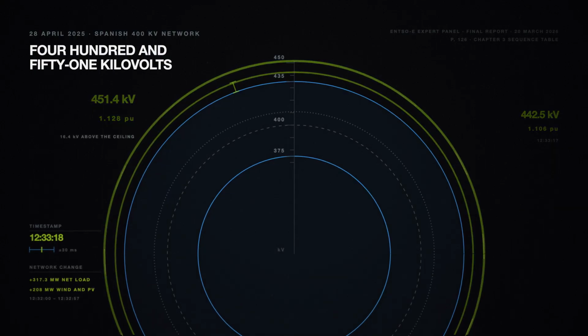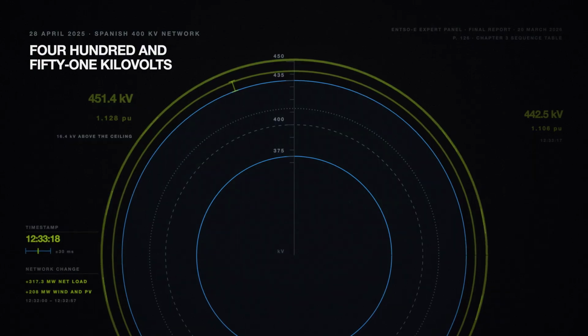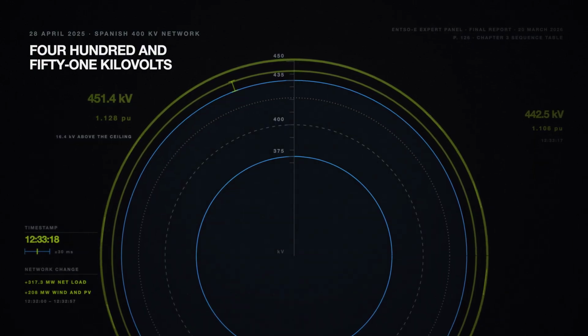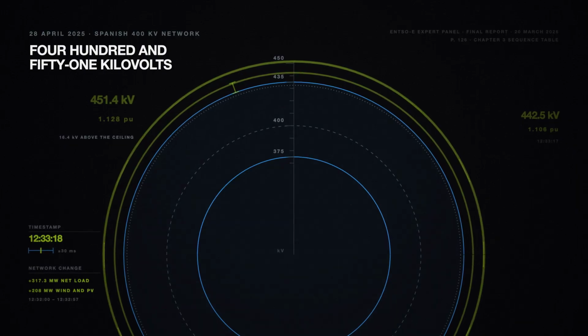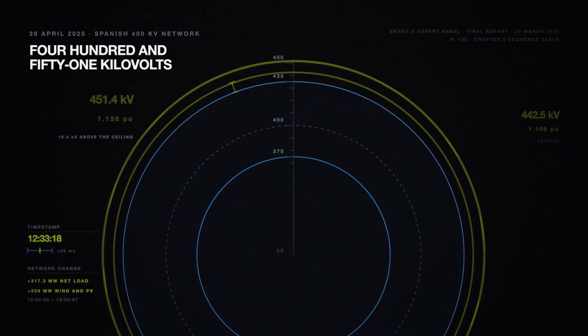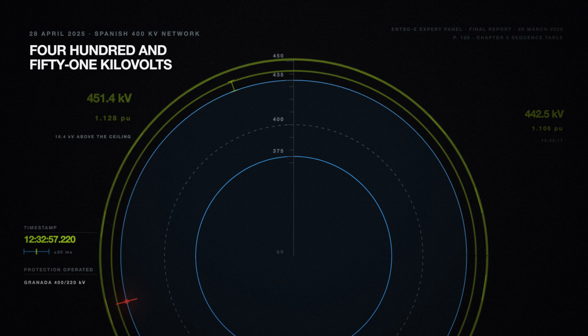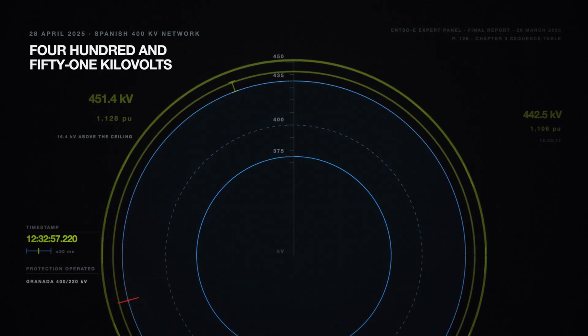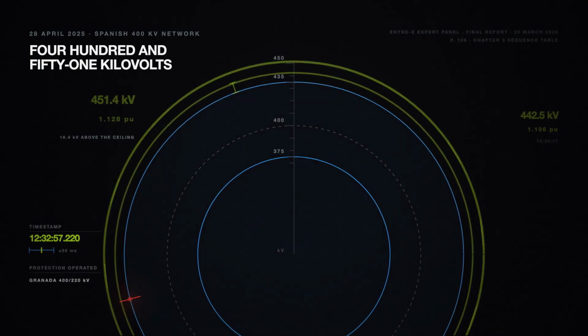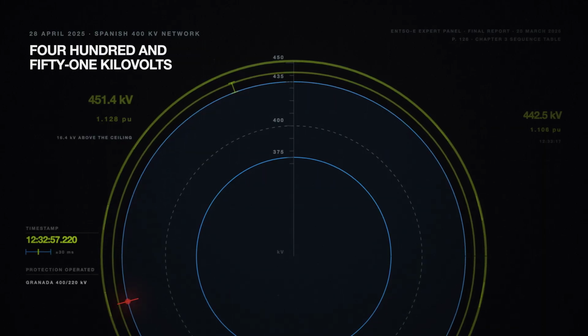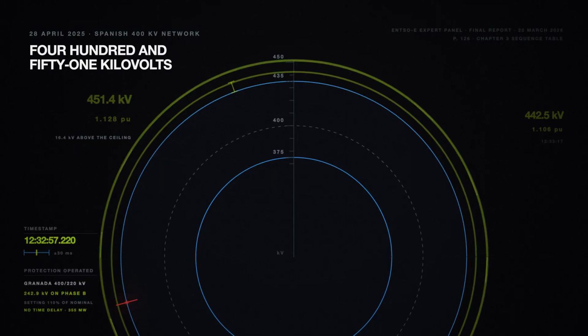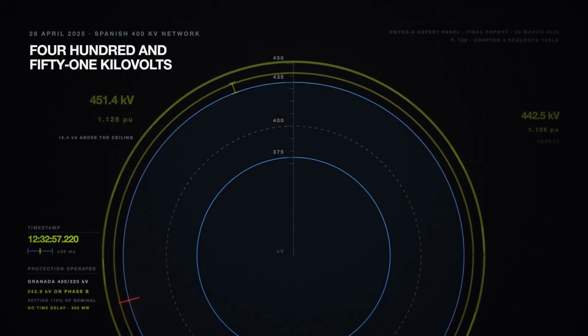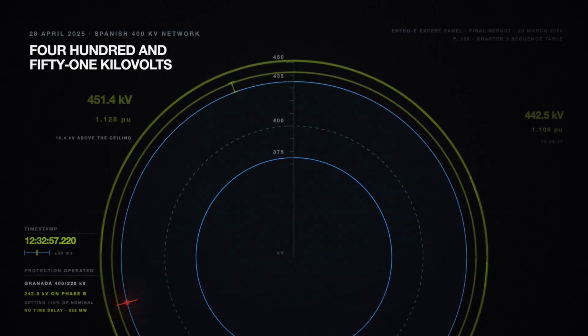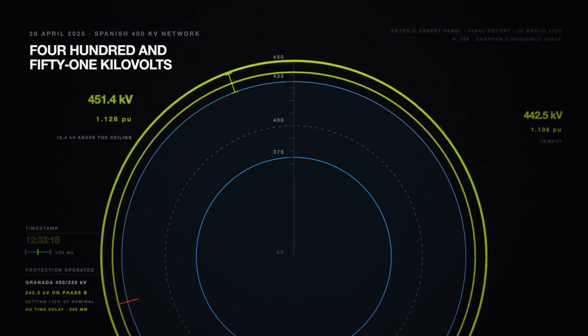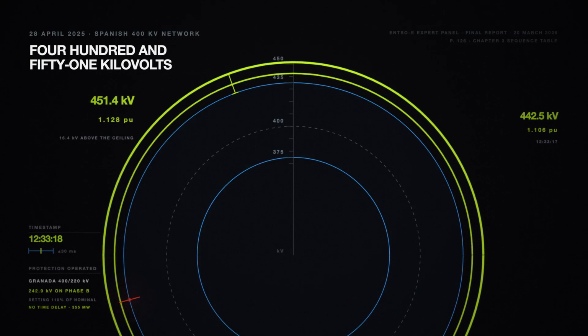Before any of that, a slow drift. Between 12:32 and 12:32 and 57 seconds, net load on the peninsula rose by 317.3 megawatts, and wind and solar generation by a further 208. Then the first protection device in the sequence operated at 12:32 and 57.220 seconds. A 400 to 220 kilovolt transformer at Granada. Its overvoltage relay saw 242.9 kilovolts on phase B against a setting of 110% of nominal, with no time delay at all. 355 megawatts came off the system. Just under 30 seconds after that relay operated, the peninsula was dark.